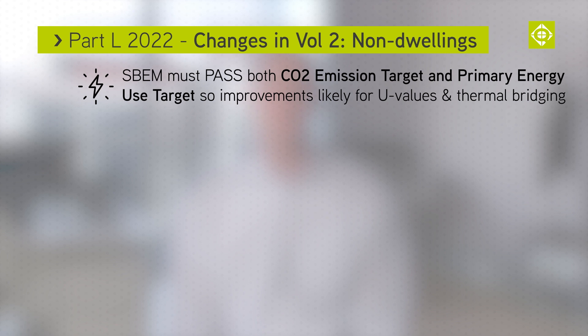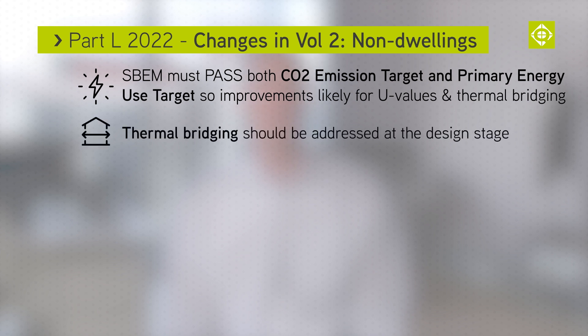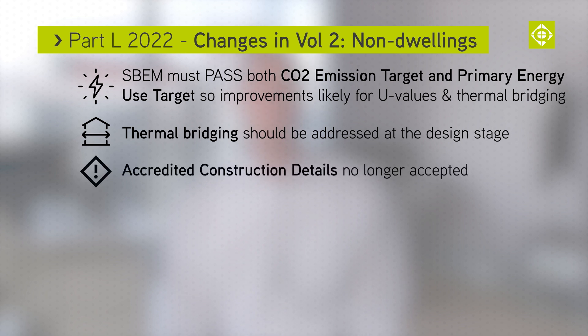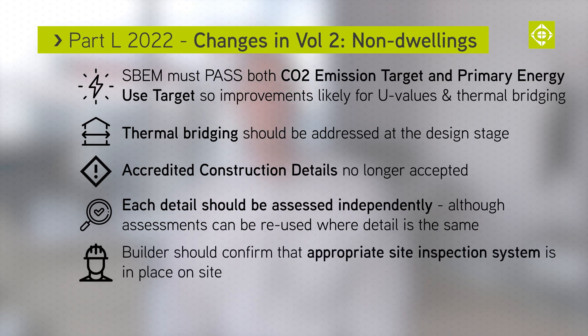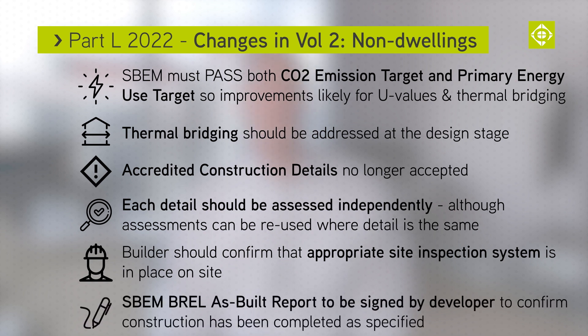Volume 2 of the new Part L relates to buildings other than dwellings. Key changes include that the SBEM is now required to pass both the CO2 emission target and a new primary energy use target, so improvements are likely to be required for both U-values and thermal bridging. Thermal bridging should be addressed at the design stage, and accredited construction details will no longer be acceptable for use within the SBEM calculation — instead each detail should be independently assessed, though assessments can be reused where the detail is the same. Builders should confirm an appropriate system of site inspection is in place, and the SBEM as-built report should be signed by the developer to confirm construction has been completed according to specification.